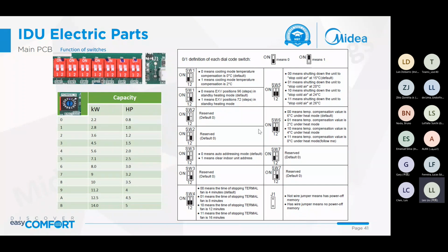Okay, the DIP switch has different functions. We can set the DIP switch for some basic settings, capacity, thermal function in heating mode, and temperature compensation. Also, there's a jumper for the auto restart function. Without the jumper, it has the auto restart function, and with it means no auto restart function. You can remove the jumper by yourself.